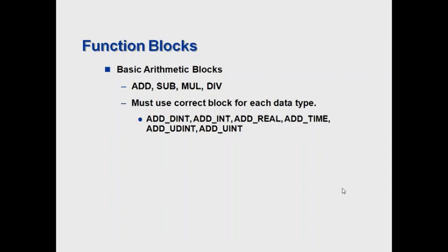It used to be that you had to use the correct block for each data type in older software, such as the ADD integer or ADD real. But in the newer Unity software, you can simply use the ADD block and it will automatically determine which data type it's adding. Of course, you can only use the same data types. For example, if you're adding a real, you must have a real as both inputs or multiple inputs and the output must be a real data type as well.